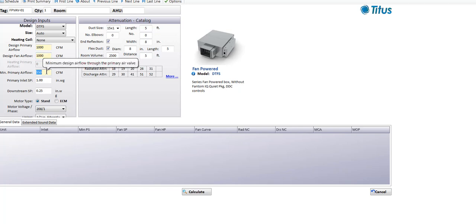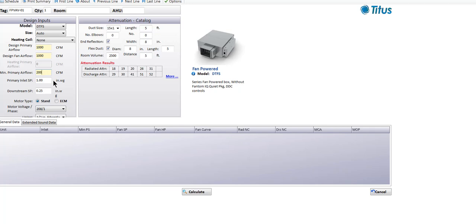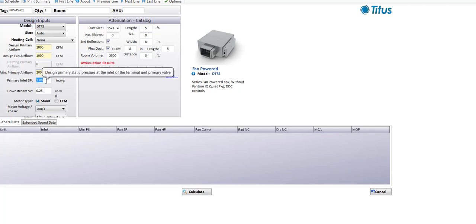We've got to put in a minimum cooling CFM — let's say that's 20% or 200 CFM. Our primary inlet pressure once again defaults to one inch of pressure. That might be appropriate for a parallel fan box, but for a series fan box, it actually acts like a booster on the air handler. I see a lot of people operating series fan boxes as low as half an inch on the inlet pressure, which can allow you to save a lot of energy at the air handler.